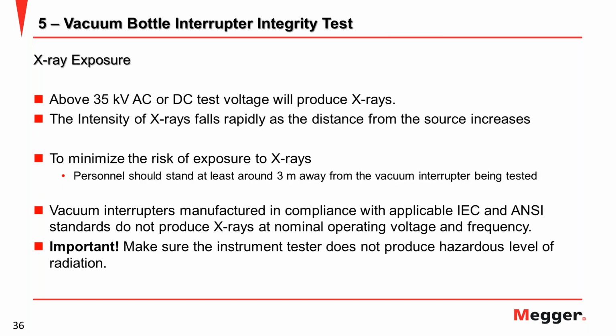And also just for your information, to be careful, because if you talk about the vacuum circuit breaker or vacuum bottle, if you test above 35 kV, AC or DC test will produce X-rays. So this is also one consideration to choose the equipment tester to avoid the X-ray produced when you do testing, especially above 35 kV AC or DC. To minimize the risk of exposure to X-ray, personnel should stand at least 3 meters away from the vacuum interrupter being tested.